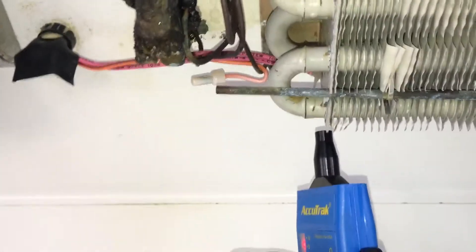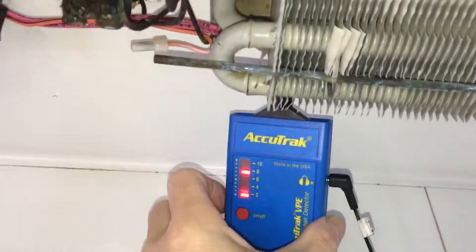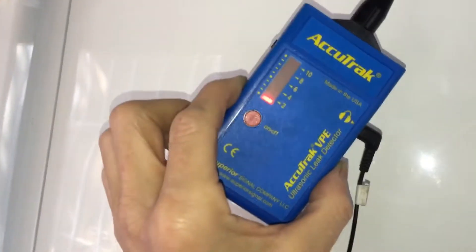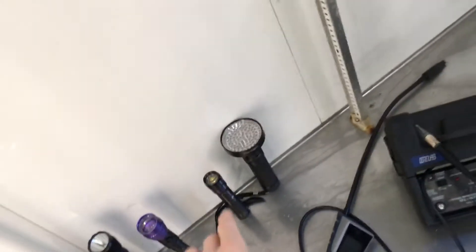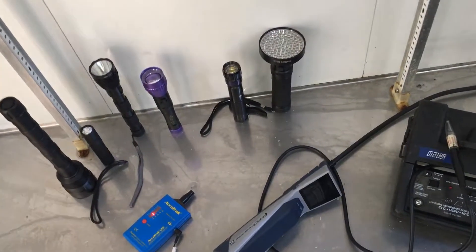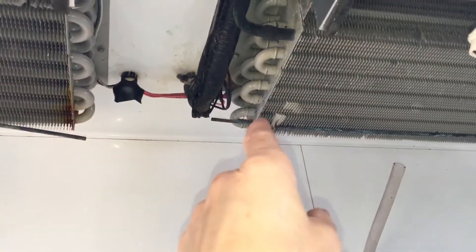You have to adjust your human senses and your hand-eye coordination and know when you've bumped something, or when your elbow or external noise can set these off — but they are really good in certain situations. This is R134 and without sticking my pressure gauges on here, given the ambient temperature sitting outside overnight, I'd say the pressure in the system is about 65 psi. If you wanted to pressure test this and couldn't get it to leak with refrigerant, you might want to pump the system up with nitrogen to 150 psi to get better results. The UV dye shows a little trace from running, since I put dye in a couple days ago. I did pressure wash twice because it was so dirty.